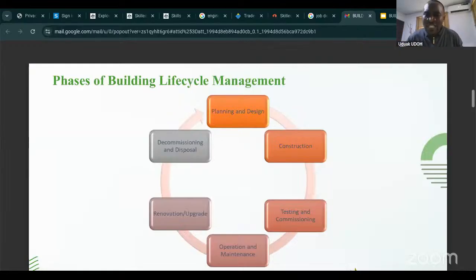Sometimes you install a unit and before it starts cooling as it's supposed to, probably from the manufacturer's manual it's estimated that within 5 to 10 minutes you're supposed to reach a particular ambient temperature. But are you actually getting those temperatures? That's when we now come to commissioning. So after you've checked all that and you feel the items installed are working well, then you power that unit. After powering the unit, you are commissioning it, and now you are checking if that unit serves its purpose.